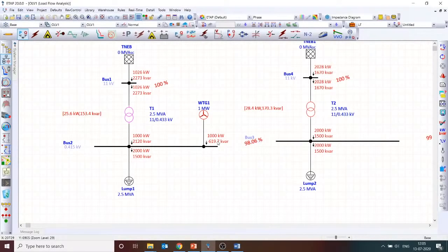Okay. So it is one moment with a peak demand and a peak wind generation. That's the scenario which I am comparing. Only one scenario. There could be many scenarios like peak wind, less load, peak wind, average load, and so many possible operating configurations. For that you can use a time domain load flow. I am just capturing only one moment of large dynamic power systems. Right. So 25.6 here also, if you look, the losses are almost the same.